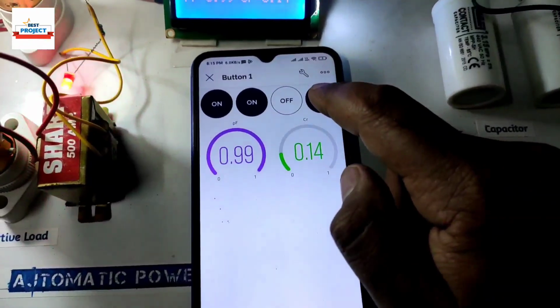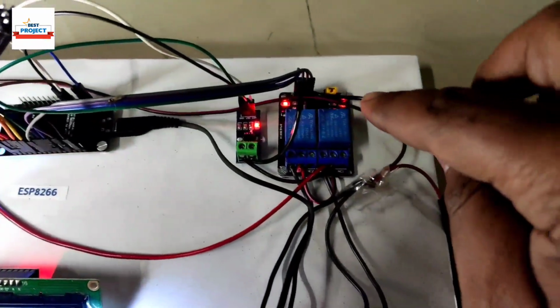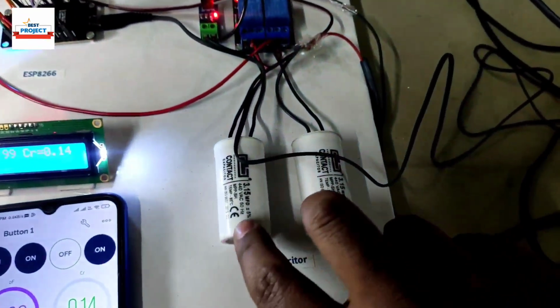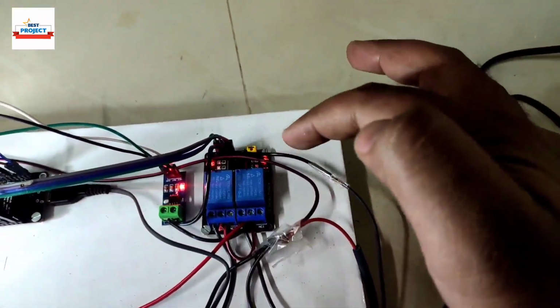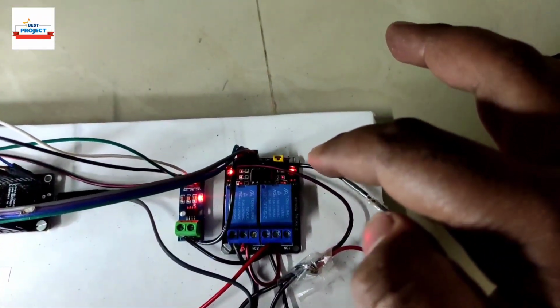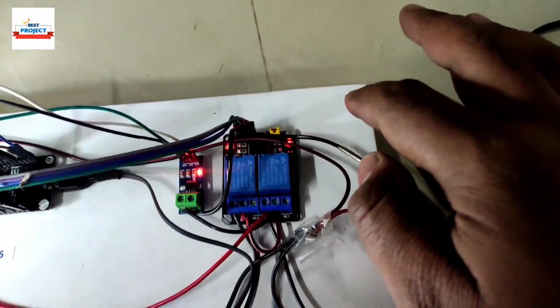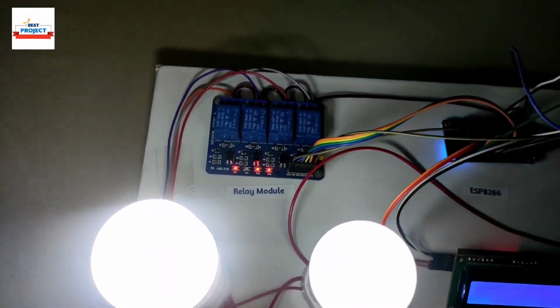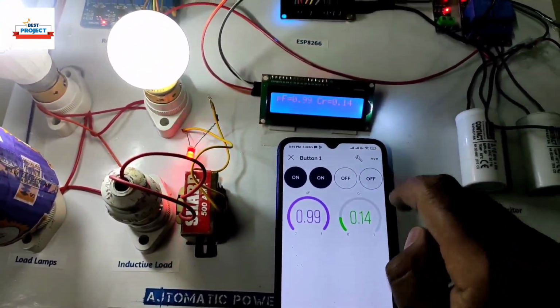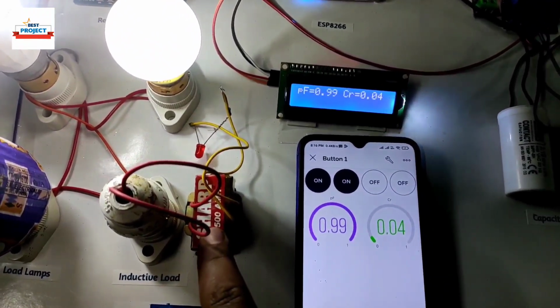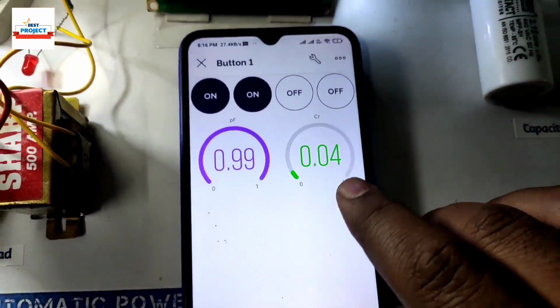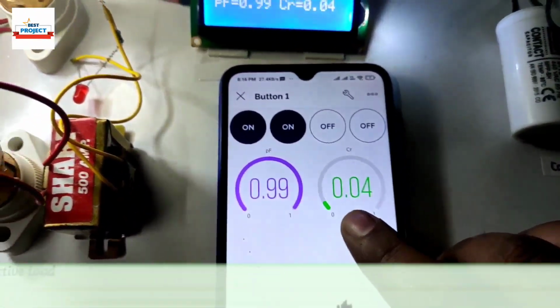Okay, let's turn off this inductive load. So you can see both of the capacitors are on. You can see from here this red light indicates which capacitor is connected in parallel to the line. So you can see, okay, and here on the load side also. Okay, so let's turn off the inductive load. See, the inductive load has turned off, and you can see the power factor correction was 0.04 only, because these are only resistive loads.